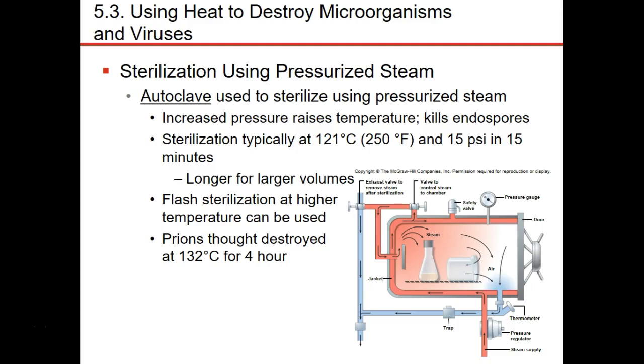Though we can kill off the majority of all microbes, prions cannot be destroyed in the autoclave at that temperature. Prions are those infectious proteins. You have to heat the environment up higher — to about 132 degrees Celsius — and leave them there for four or more hours, and that still may not destroy the prion.